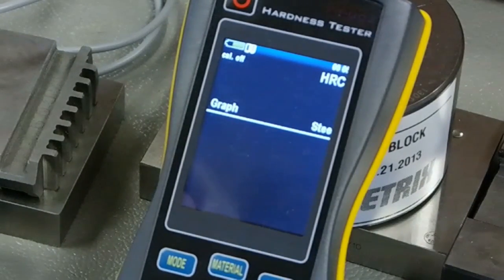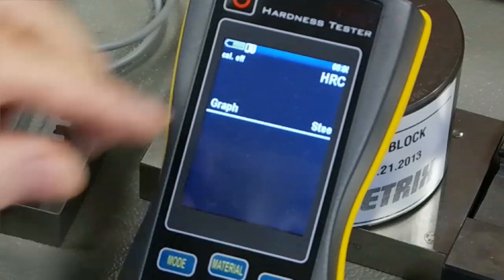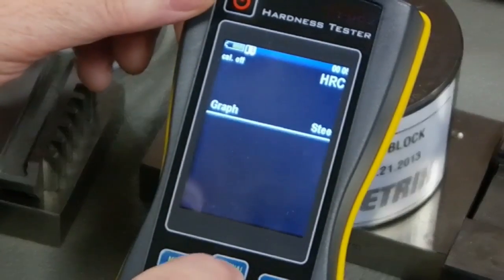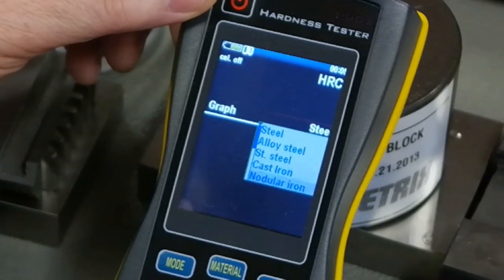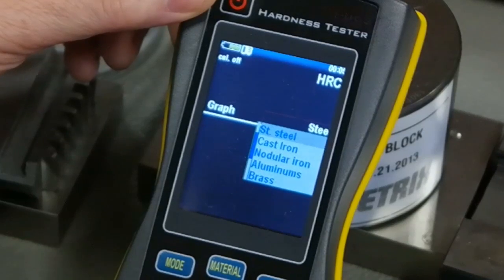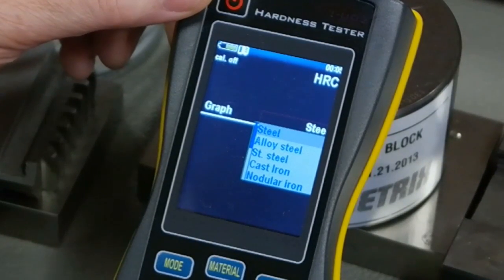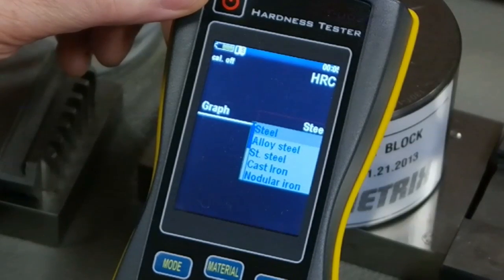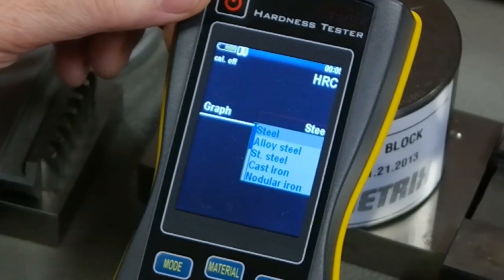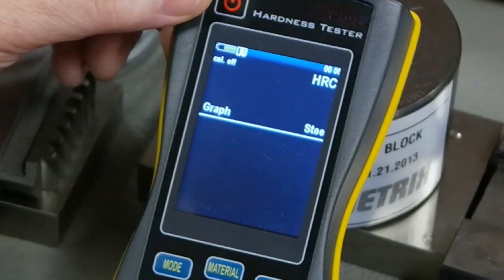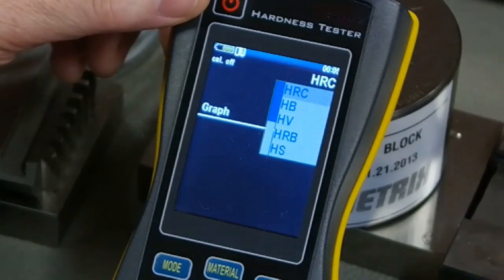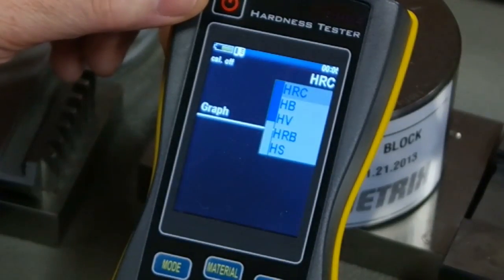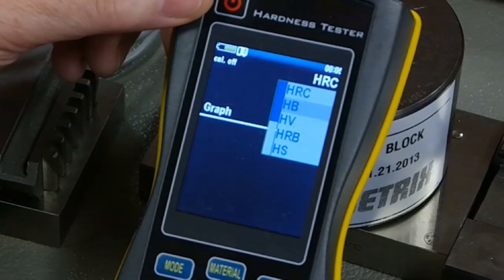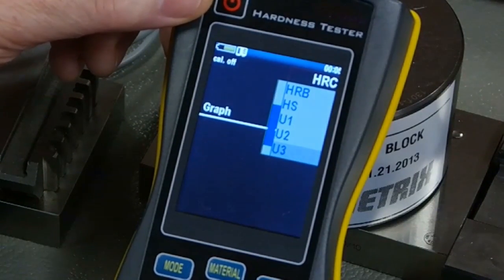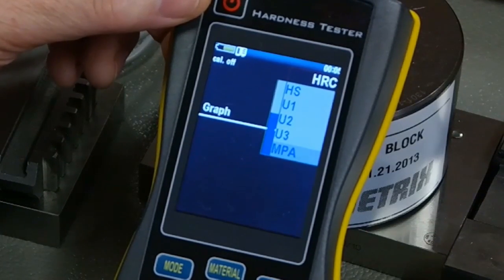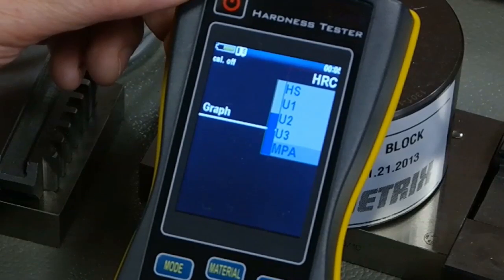Right now I have HRC as my setting, and I'm going to be testing against steel, and I'm in graph mode. If I want to change the material, I just hit the material button and I can scroll through the different material types. And as I said before, we only configure, in fact any ultrasonic tester company does, any device for steel only. You can calibrate for your own materials, all you just need is some samples of the right hardness. So I'm going to reselect that, and then under the scale is for the Rockwell C, Brinell, Vickers, HRB, Rockwell B scale, Shore. You've got your own user-defined fields, and we can even do the tensile strength of the material based on the Brinell hardness of the material.